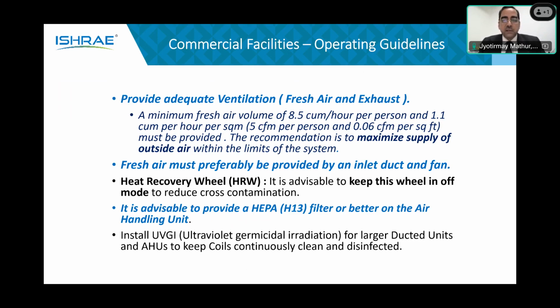In addition, on VRF systems we highlighted the need for higher air filtration. HEPA filter is what we recommended, or if they have better filtration than H13, we were welcoming that. In addition, for air handling units, we suggested using UVGI for disinfection, and wherever there's a possibility of water collection, use UVGI for disinfection there too.